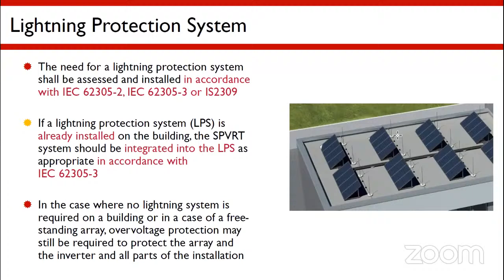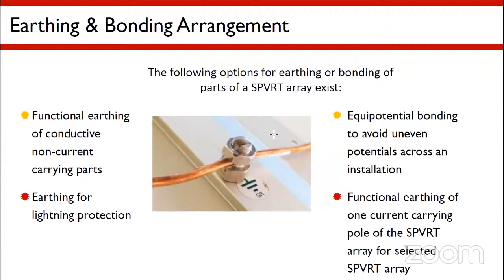Then earthing and bonding. Earthing and bonding is another important factor, because it's not only about connecting panels together, it is also to provide safety. Since high voltage DC is generated on the PV array side, if any problem happens, the discharge of the fault current to the earth is a very important and critical factor. That is why all the PV modules are interconnected by cables or copper rods. The main intention is to provide safety and equipotential bonding across the array installation.